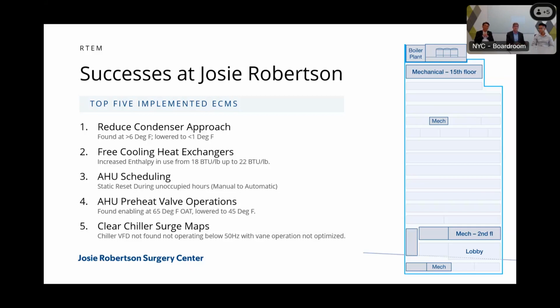So we actually underwent a test with the operators at the site where they did a scheduled setback. We observed it. We didn't see any red herrings in turning down some of the air handling units. And then we worked with the site through this manual operation to find those sweep points. And eventually that AHU scheduling was automated. So now there's no touch. And with the benefit of utiliVisor and the RTEM system and services, we are continually watching it.